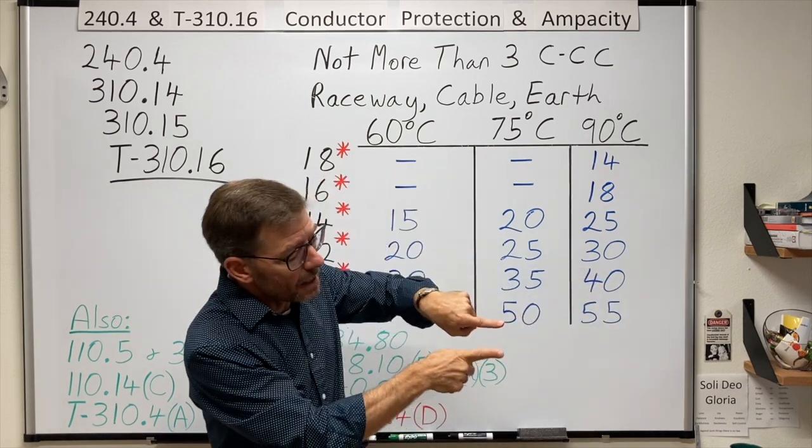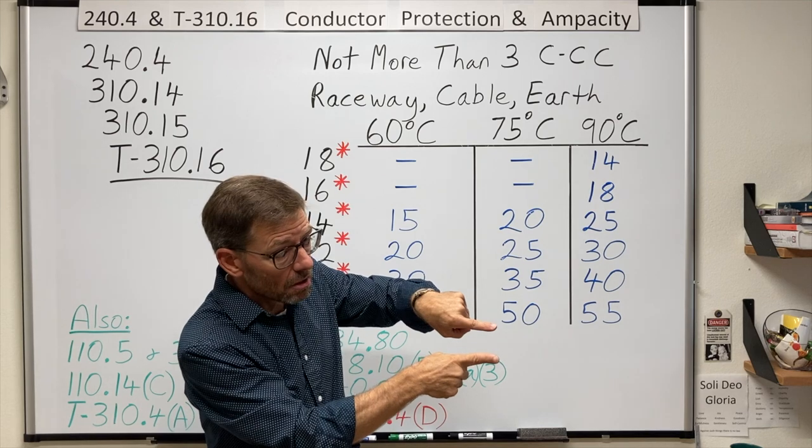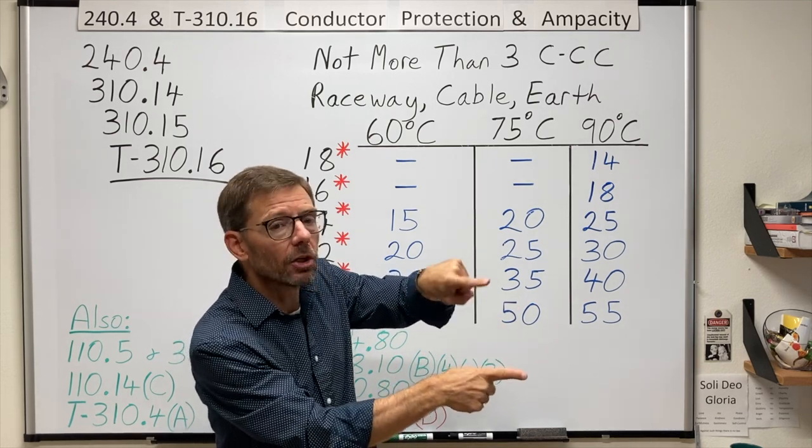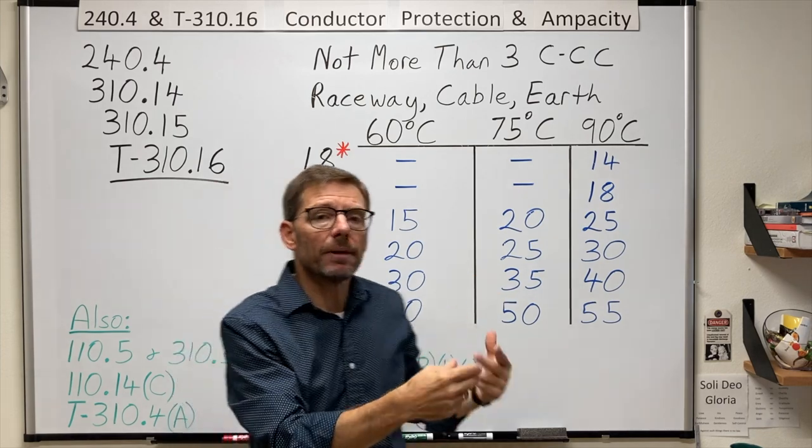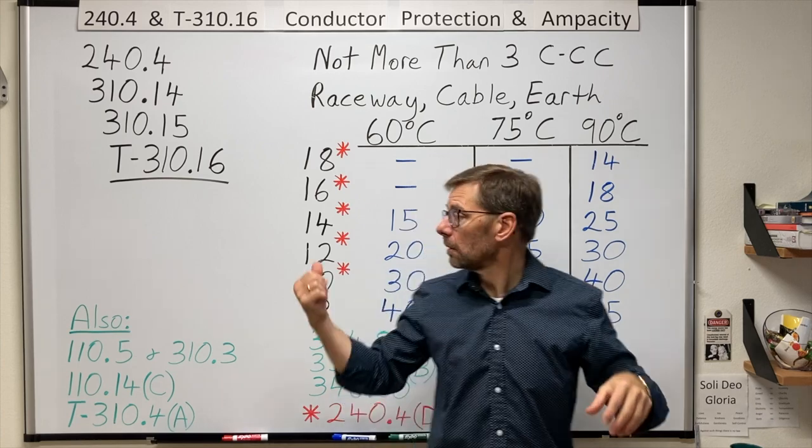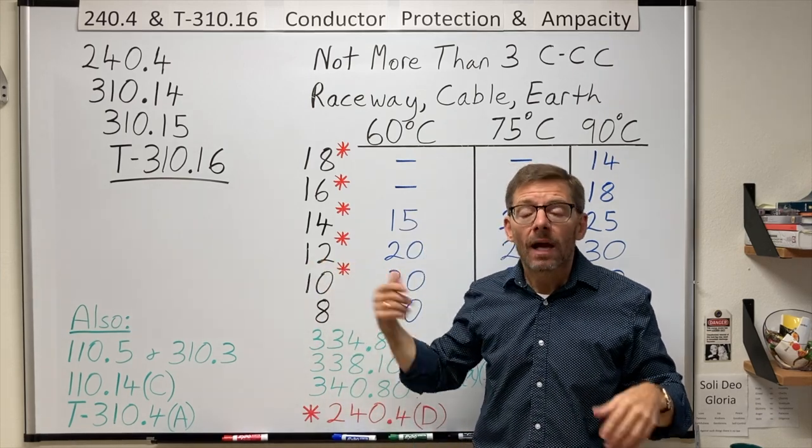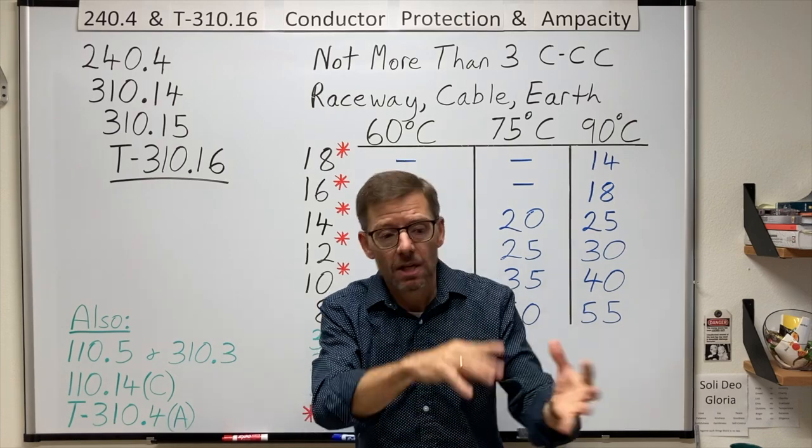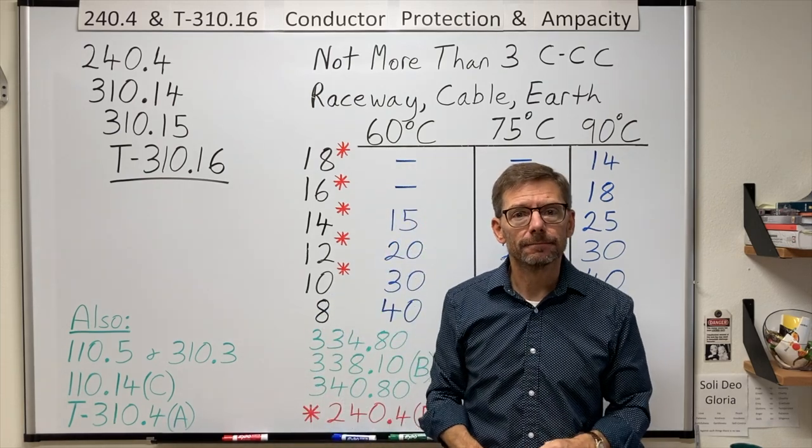Why do we have to have a smaller limit of ampacity on aluminum conductors? Again, it goes back to our theory. Aluminum has more resistance than copper, and is therefore less conductive. So given the same size wires with the same amps, the aluminum would run hotter than the copper. What it generally means is when using aluminum, we have to use a slightly bigger wire than we would with copper. And there's reasons for using aluminum. It's lighter. It costs less. But that decision has to be made.